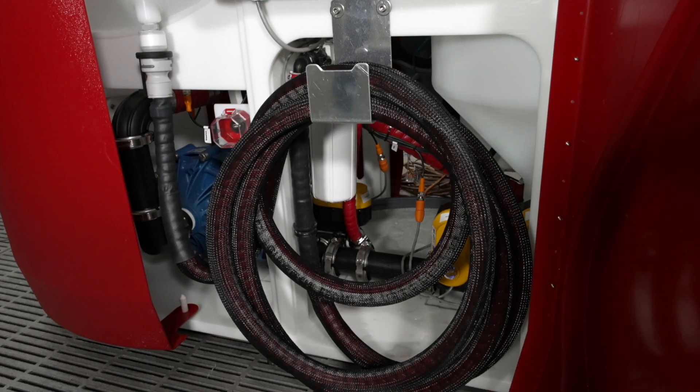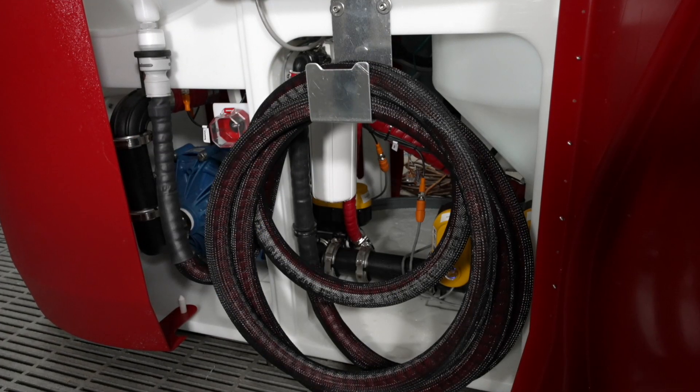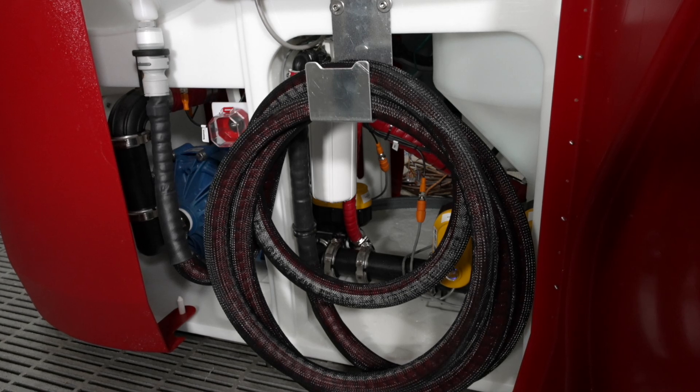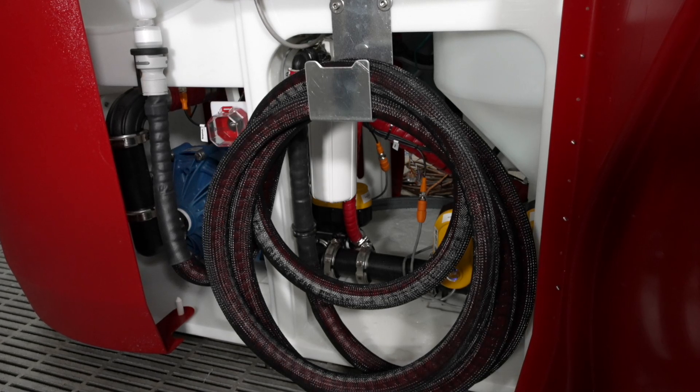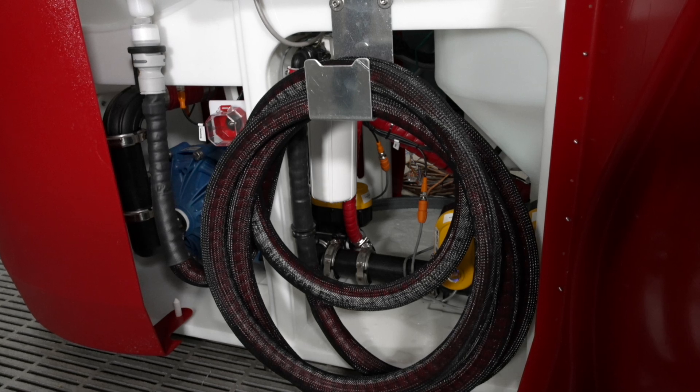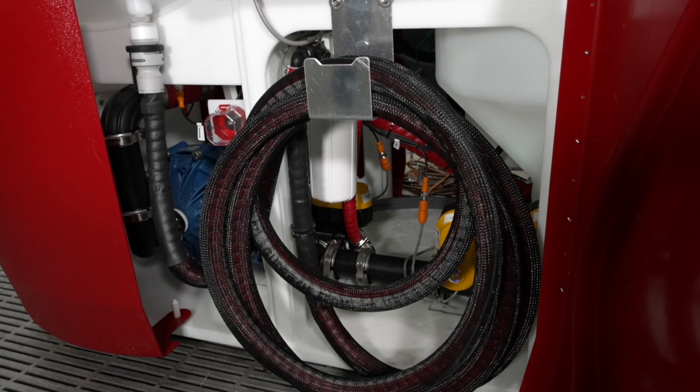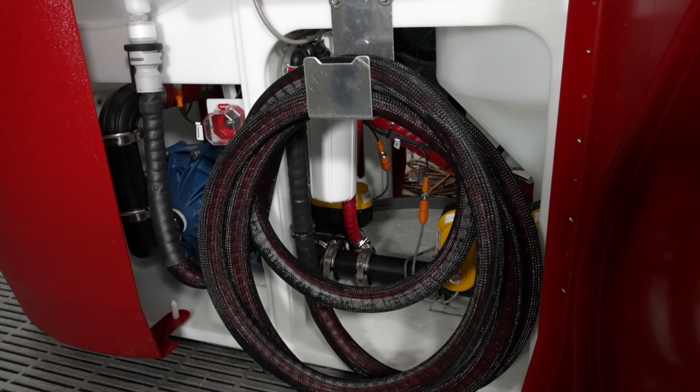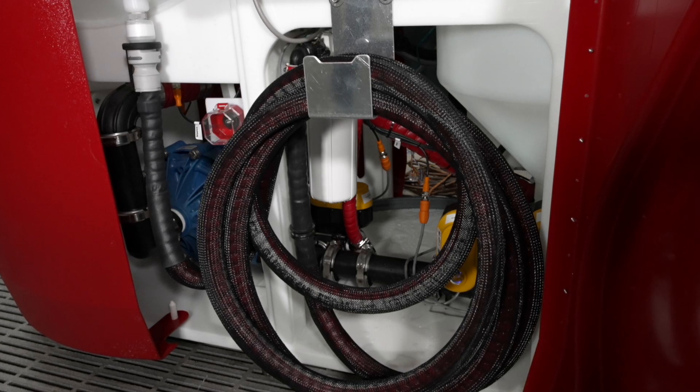Ensure that the external transfer hose located behind the access panel is connected to the Acumix prior to starting the batch and not to the storage tank. Acumix will not begin the batch cycle unless the transfer hose is attached in the proper position as shown here.